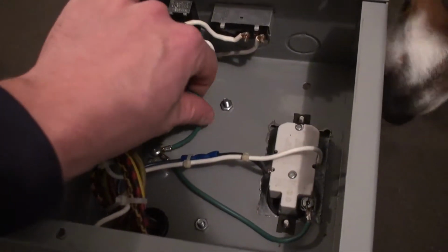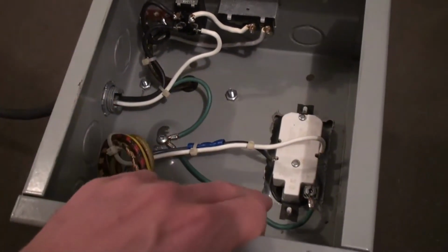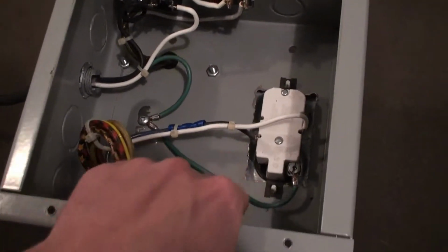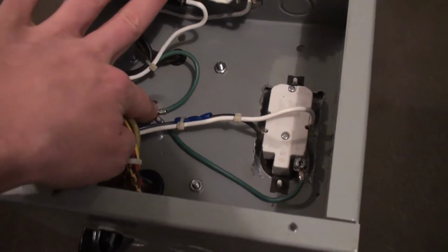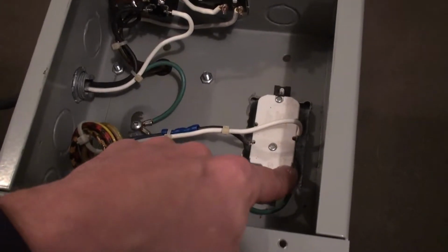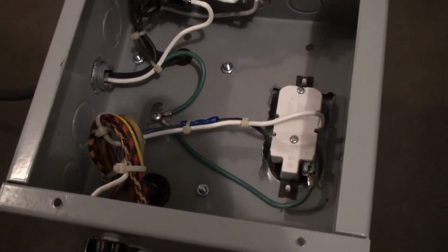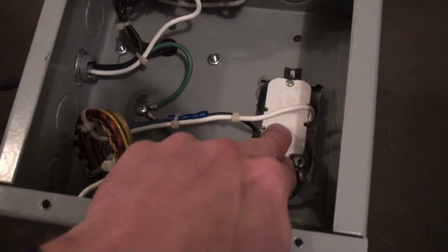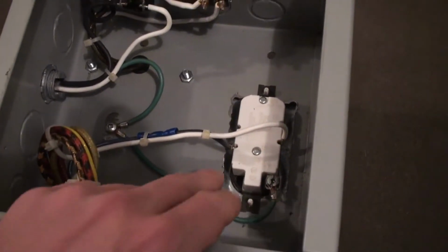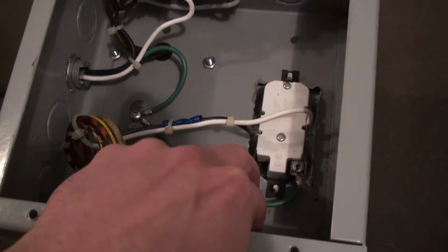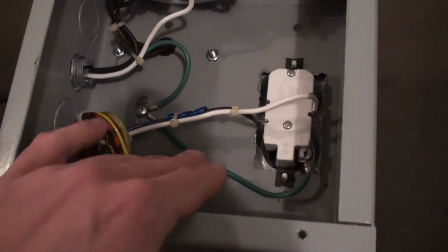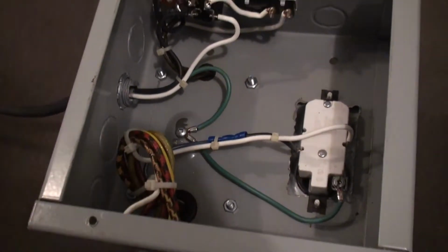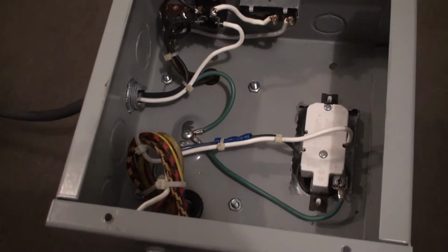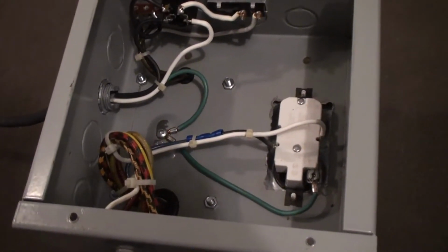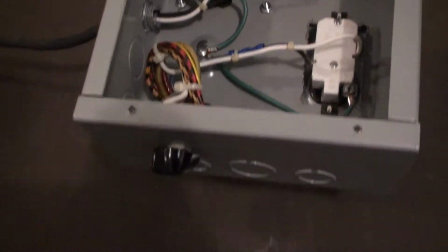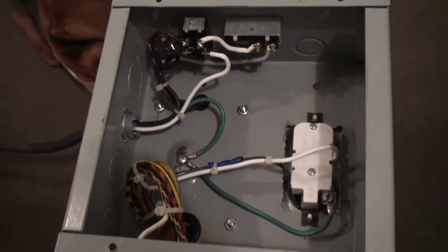The case is grounded, there's nothing wrong with that. The part that is concerning is the ground that goes from the case to the ground of the receptacle, because that means when you plug your device under test into this, basically your neutral is now going to be earth ground referenced back in the breaker panel. So this build here offers no isolation whatsoever.